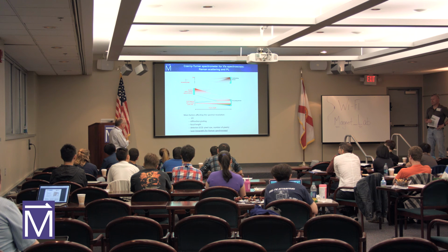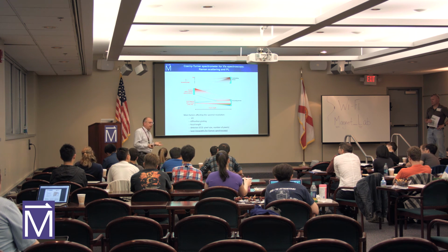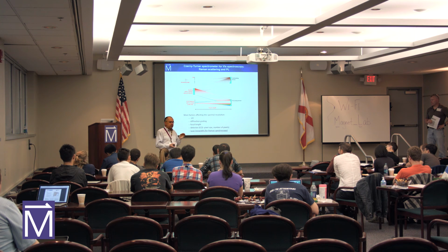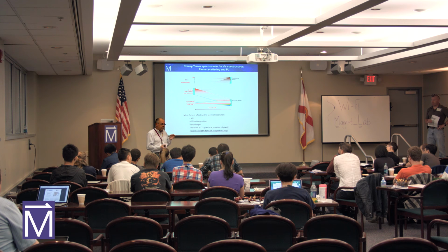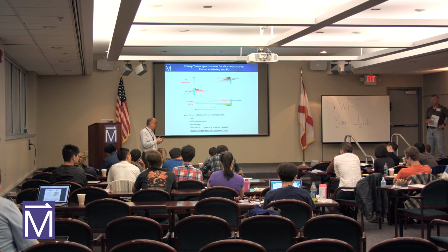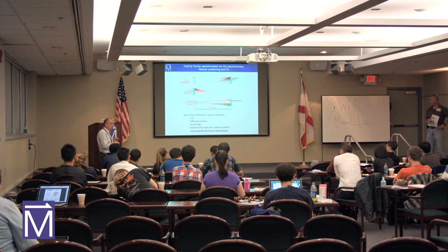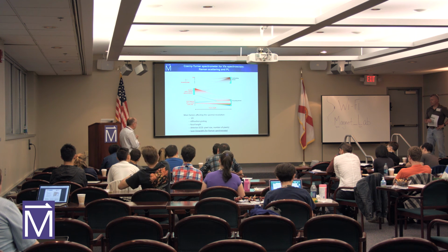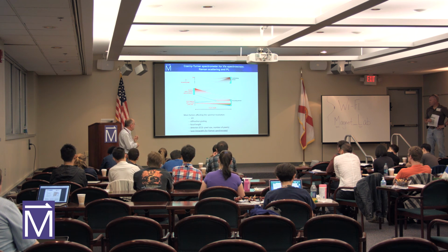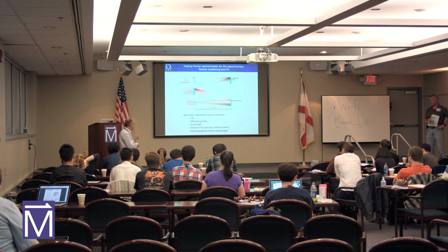Let's start here. Any detector has its size, in real life. A standard modern CCD has a 20 micron pixel width. And if you reduce it 2 times, 4 times, the signal will decrease as the square of this. It's possible, just losing your signal. Let's say this is a 20 micron pixel. Then for the highest resolution, the slit should also be opened to 20 microns. Because what's happening is that you reconstruct the image of the slit in the focal plane here. And then to achieve the required resolution there is the focal length, the dispersion. You move it 10 times, 2 times further away, and then you have a big displacement.